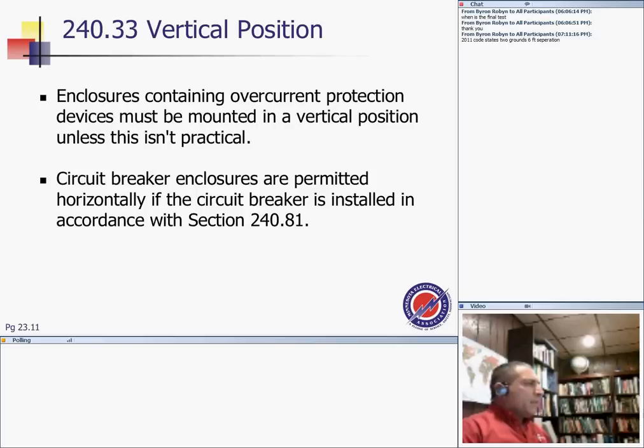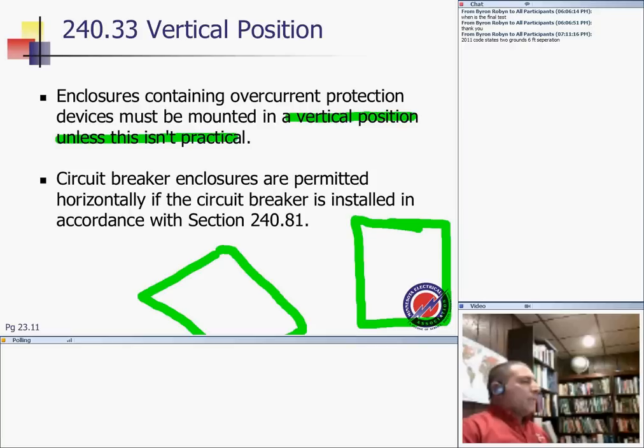It must be mounted vertically, including the panel that has the overcurrent device, guys. They want it to be in a vertical position unless this is impractical. So you cannot put my panel this way. Mostly the panels are to be mounted vertical. There are some exceptions, but the idea is you put your panel vertical.